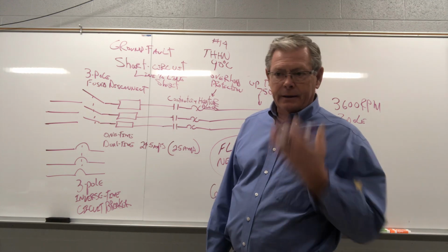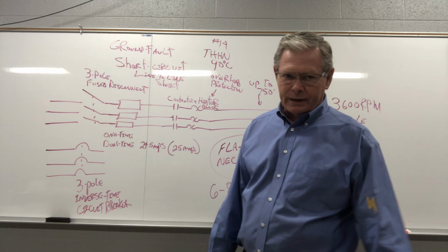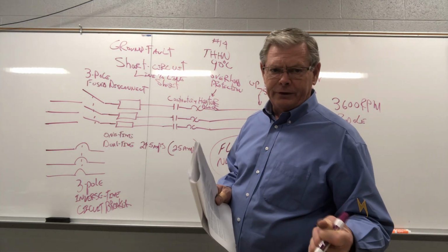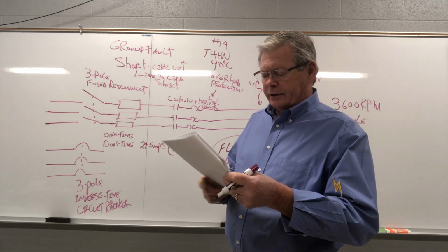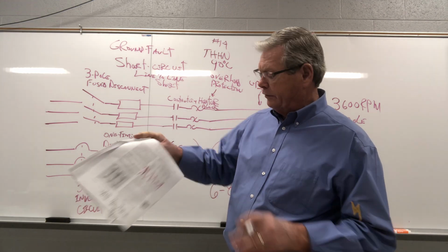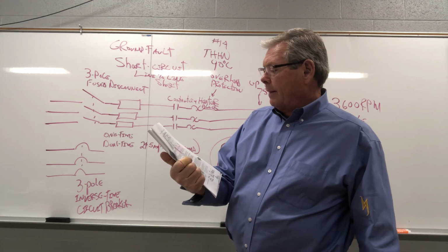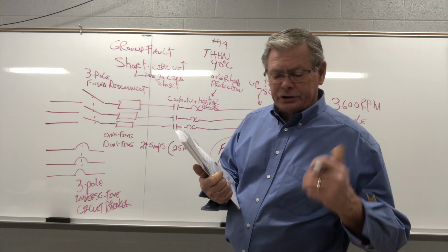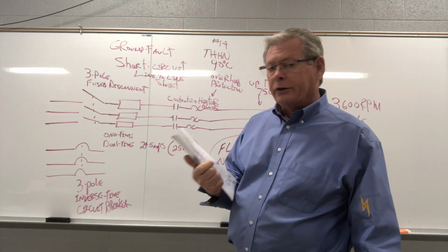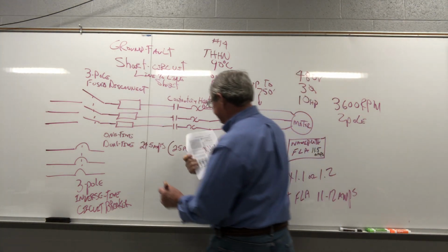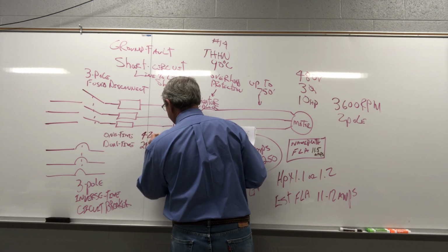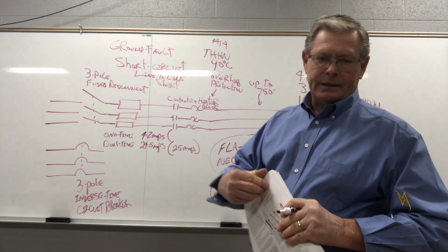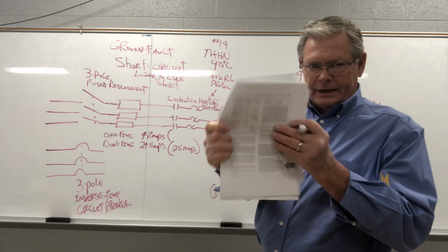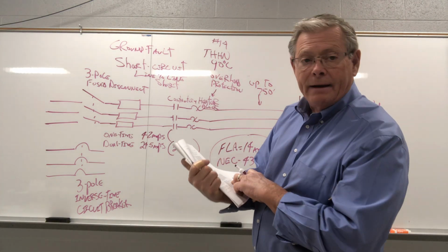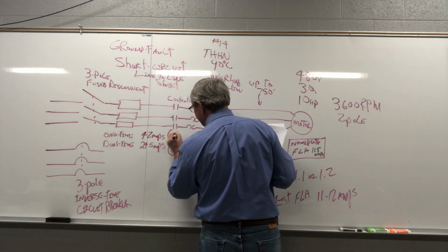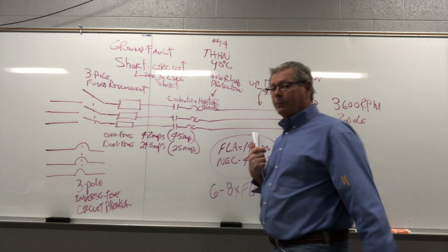So let's say that it's midnight and you blow fuses going to this motor. You change the motor out, it's burned up, and you don't have dual element fuses in the storeroom. The code lets us use a different multiplier for a single element fuse because they're not built to overlook the starting current. So the multiplier for a non-time delay fuse, or a single element or a one-time fuse, it's all the same, is 300%. And 300% times 14 is 42 amps. Now, 42 amps, I can tell you, is not a standard size fuse. So if we look over here and look for 42, I see a 45. So we can use a 45 amp one-time fuse and still protect that motor circuit.